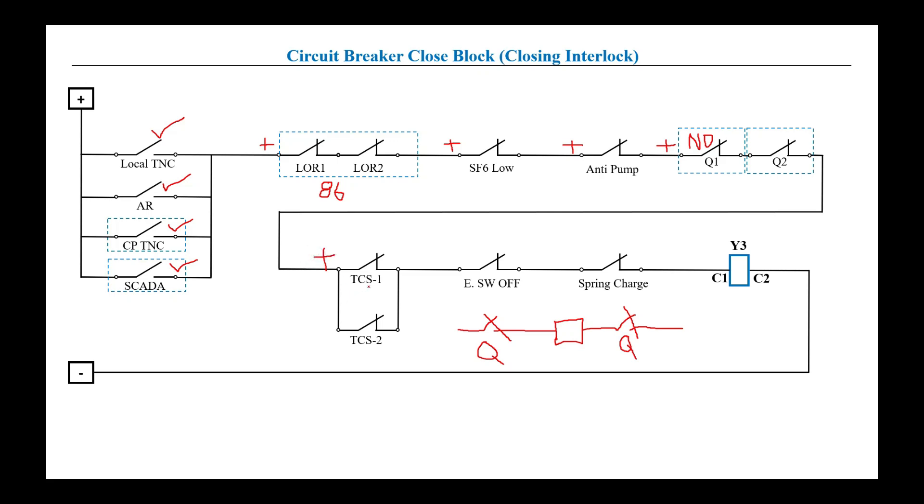The next check is TCS — trip coil supervision. We have two trip coils: trip coil one and trip coil two. If any one of the trip coils is healthy, positive will pass through. Only if both are faulty will these points open and block the positive. If trip coil two is healthy it will extend positive, or if TCS one is healthy it will extend. If both are healthy, positive will certainly pass through.